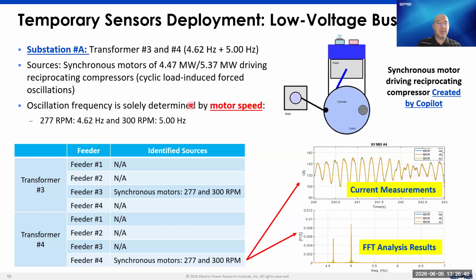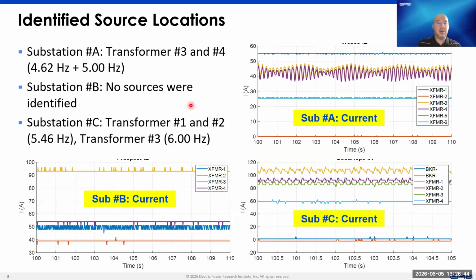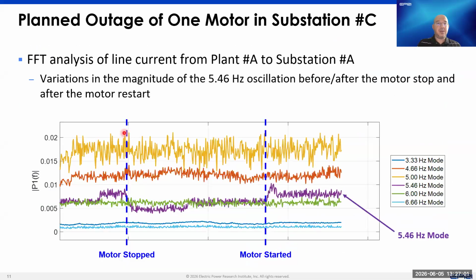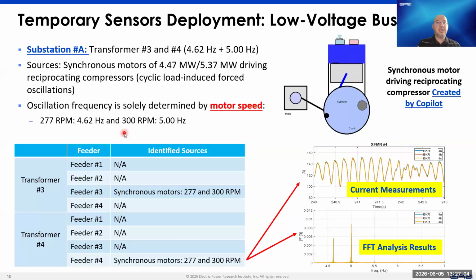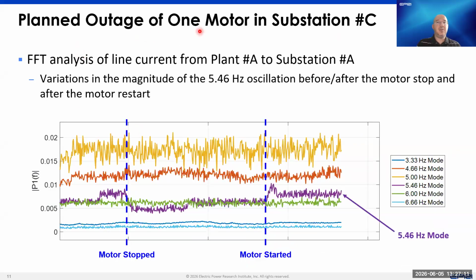And for the other substations, for substation B, we said there were no motors. In substation C, they had motors there, and they were introducing the 6 hertz and the 5.46 hertz oscillations. So that's basically the analysis we did. Another interesting data set that we analyzed was during a planned outage of one of the motors in substation C. So you see here the FFT analysis of the line current from the plant to substation A during that period where we had the outage of one of the motors.